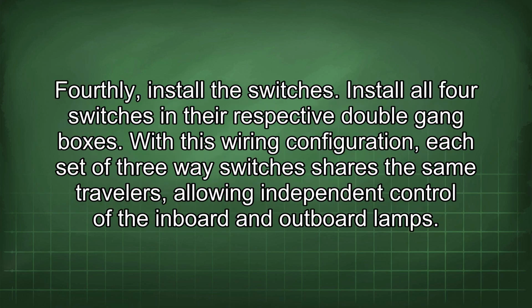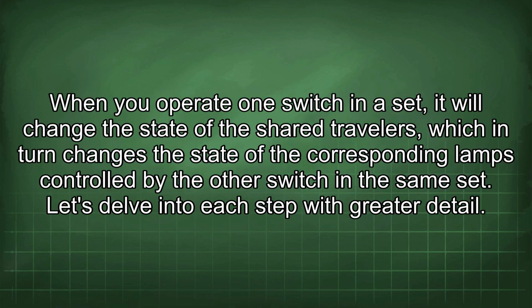Fourthly, install the switches. Install all 4 switches in their respective double gang boxes. With this wiring configuration, each set of three-way switches shares the same travelers, allowing independent control of the inboard and outboard lamps. When you operate one switch in a set, it will change the state of the shared travelers, which in turn changes the state of the corresponding lamps controlled by the other switch in the same set. Let's delve into each step with greater detail.